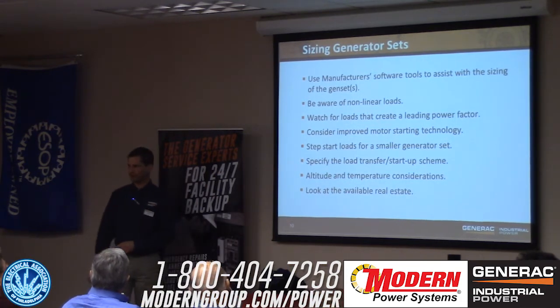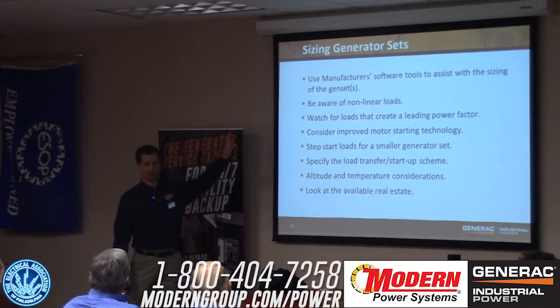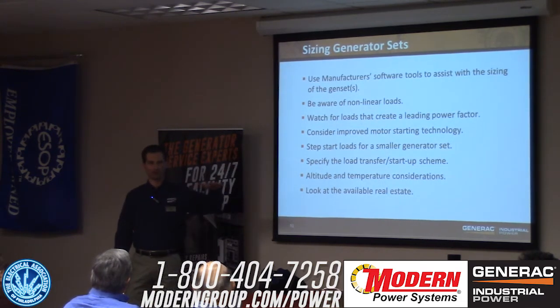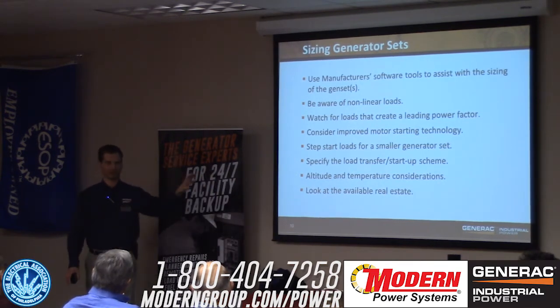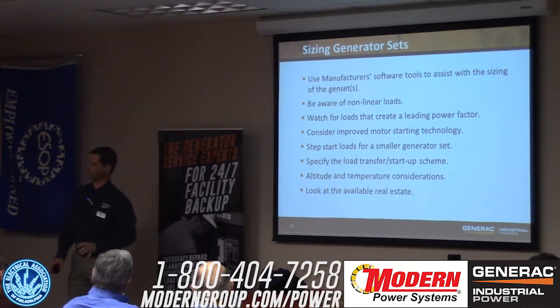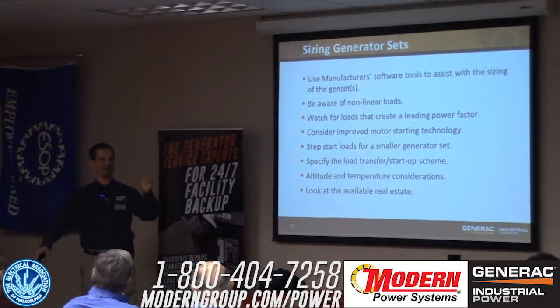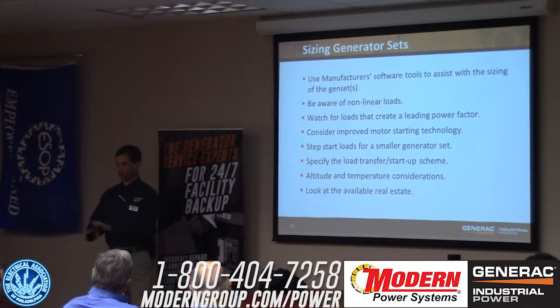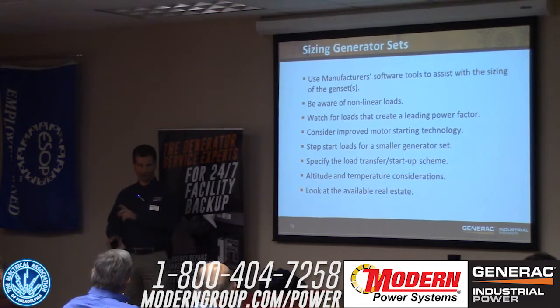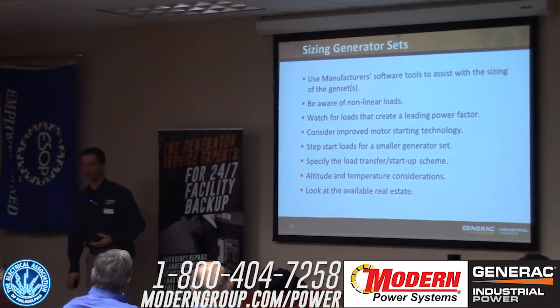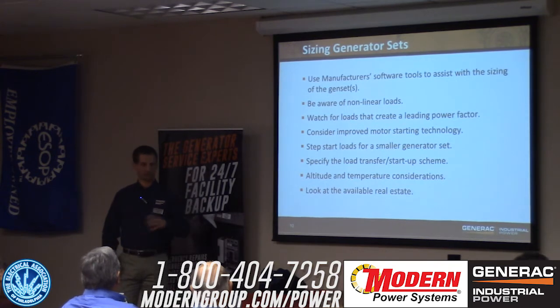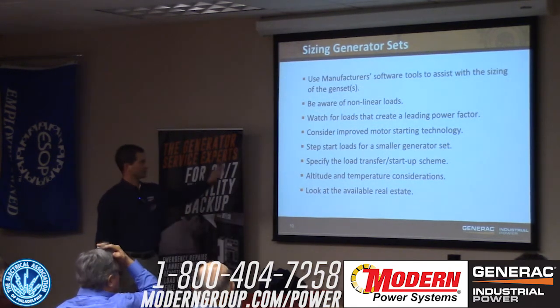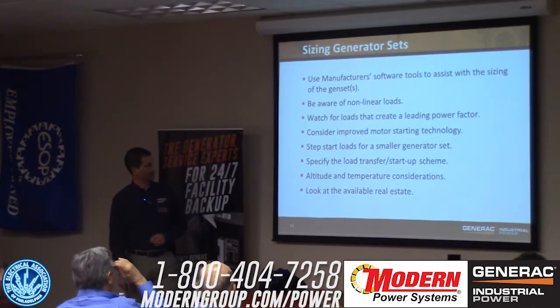Okay. You can use any of the vendor tools. For example, Generac sizing program, Power Design Pro, all the generator manufacturers have their own flavor of it. I would encourage you to use that. Even if it's what you think is a very easy load, a very easy project, don't grab that last electric bill, look at the peak demand charge and say, hey, my work here is done. You're a long way from there. That's a great place to start, to get that billing history and look at that peak demand charge for the 12 months. But what are you going to miss on that? You might miss some nonlinear loads, some horrible harmonic content. The sizing programs will help you identify that and pick that out.